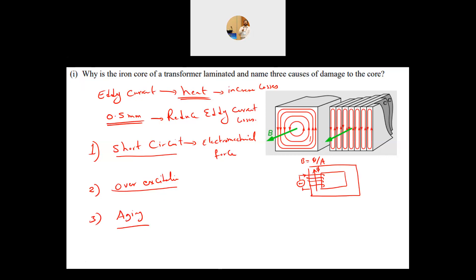The third cause is regular aging due to vibration. The core laminations vibrate constantly — the humming sound you hear near a transformer is the sound of core vibration. Over time, this 24/7 vibration damages the laminations, causing the sheets to touch each other. When the electrical insulation between them is lost, eddy currents increase, leading to more heating, further lamination damage, increased losses, and so on.